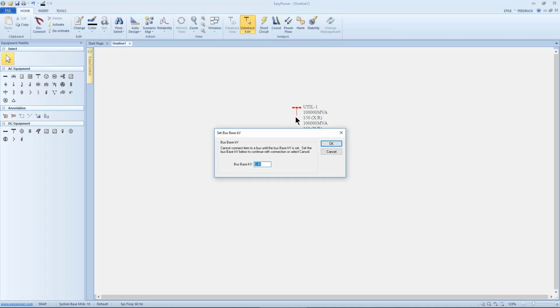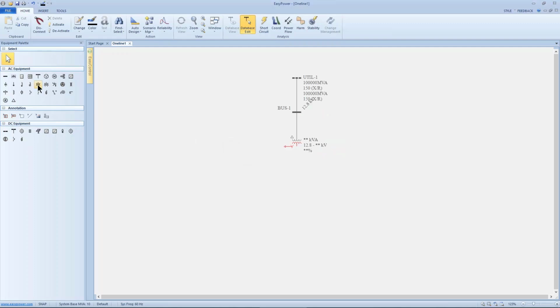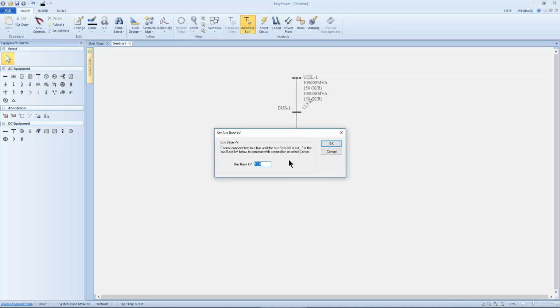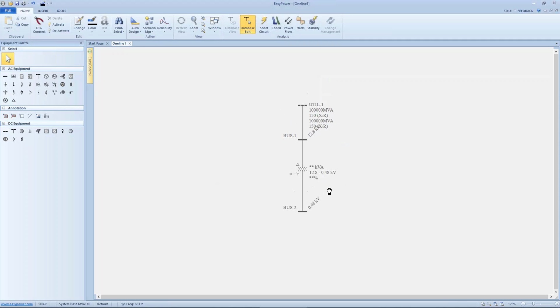He said his utility voltage comes in at 12.8 kV. Everything's in kV, so I type 12.8 into the required dialog box. He says, "Now put a plain bus on the secondary side." So I pick up the bus from the equipment palette, touch the pigtails, click a second time. He said his distribution voltage was 480 volts. I'm going to type in 0.48 for the kV.